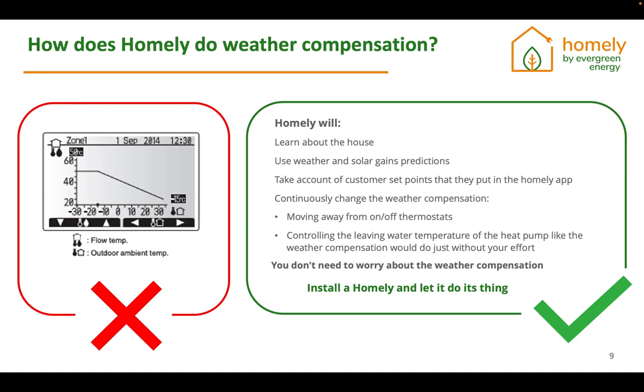As the system gets installed, Homely will start heating the house straight away, but it will work on a default standard house that we have some parameters for. Then a couple of weeks into the heating season, we'll be learning about the house. By looking at what the internal temperature is doing when we turn on the heat pump, and because we can also see how much heat the heat pump is producing and how that influences the internal temperature, we can learn this digital image of the house: how long it takes to heat up and cool down, even to the point of understanding how much heat it picks up from the sun hitting the windows and heating up the internal temperature.